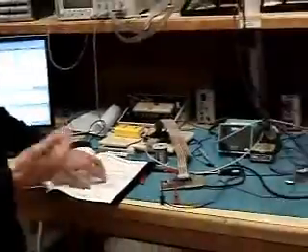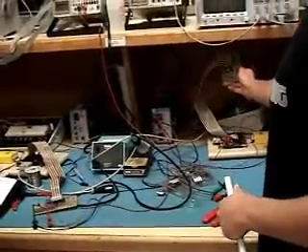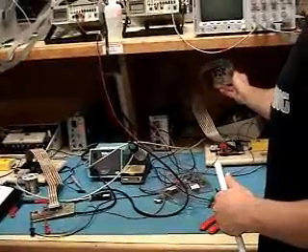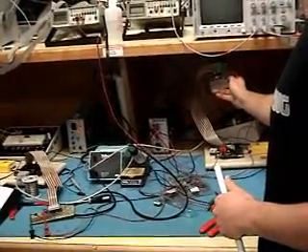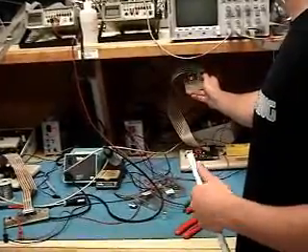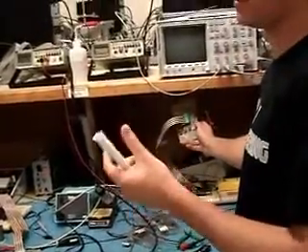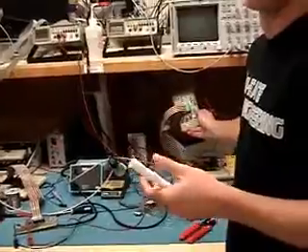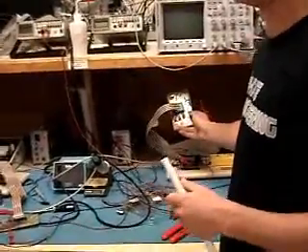What we use is a table, or a graph showing the curve, which tells how many kilopascals correspond to how many volts. We use this function to get the data, so I suppose it should be correct. Now we got 91. If I request again, now it's 88. It jumped, but it has a range between 88 and 98. A little bit of noise, I guess.